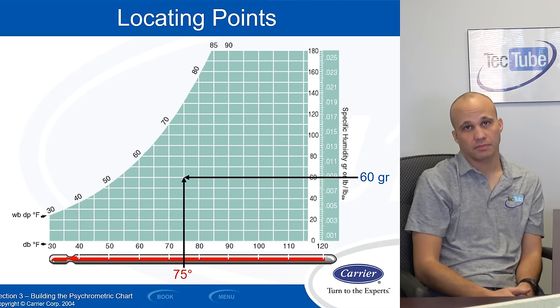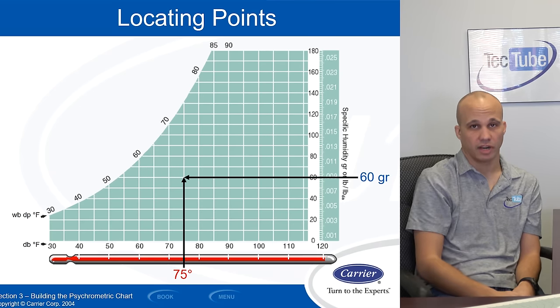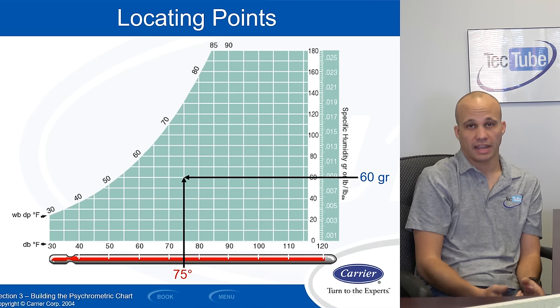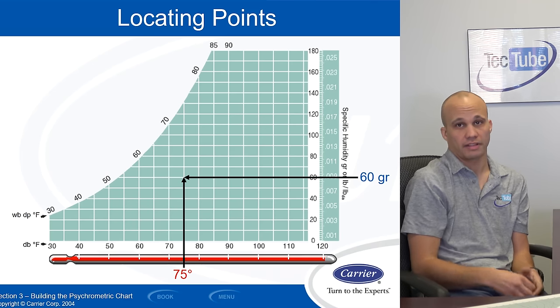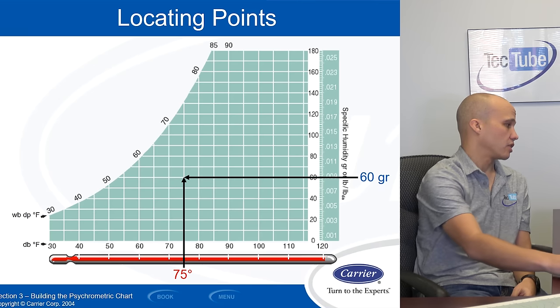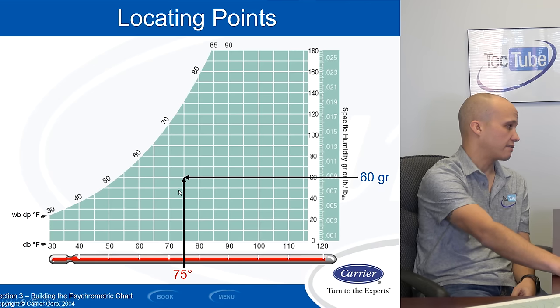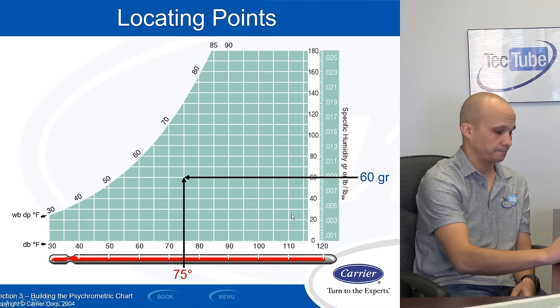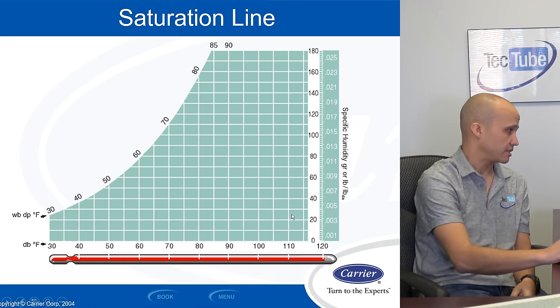So I plot one out. In order to plot something on this chart, I need to know two of those five variables. And once I know those two, I can figure out what the other three are on the chart. That's kind of the purpose of the chart. So if I take a typical room that's 75 degrees with 60 grains of moisture, I would plot a dot right there. I can do that with any of these numbers.